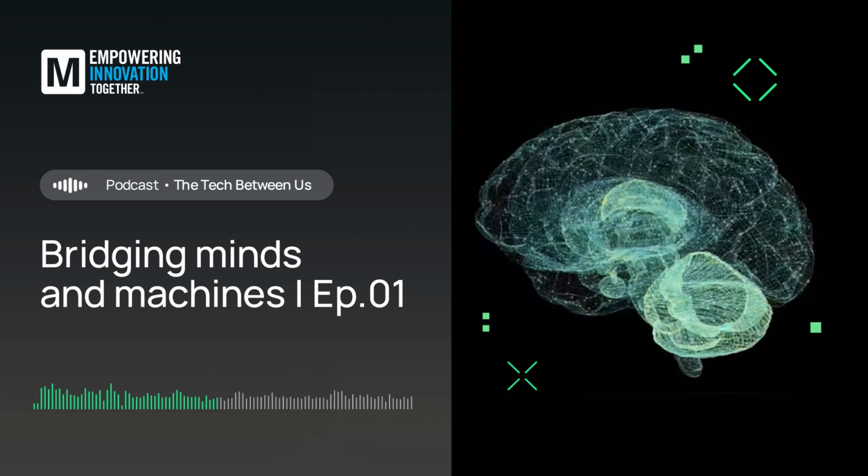When we're looking at, for example, the raw signals, when we've first got a new system set up and we want to make sure the signals look good, we're always pleased when we see big, strong signals in the 200, 250 microvolt range. But if they're smaller, then we just work with the smaller signals.